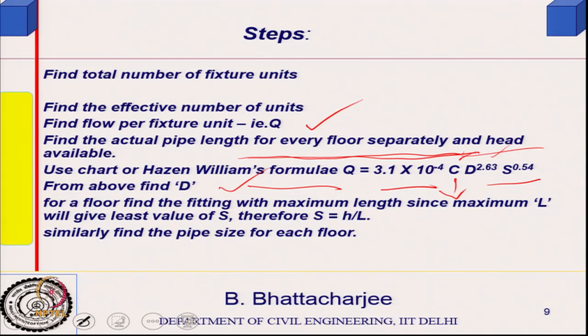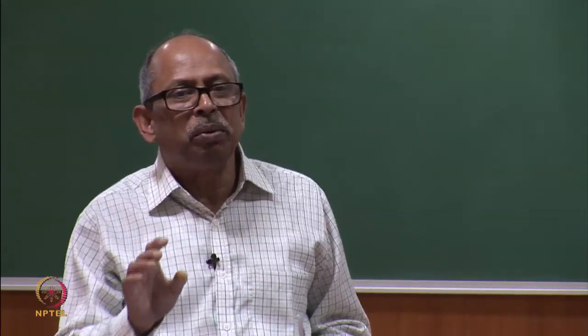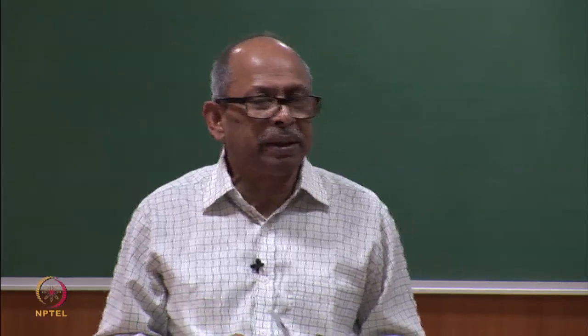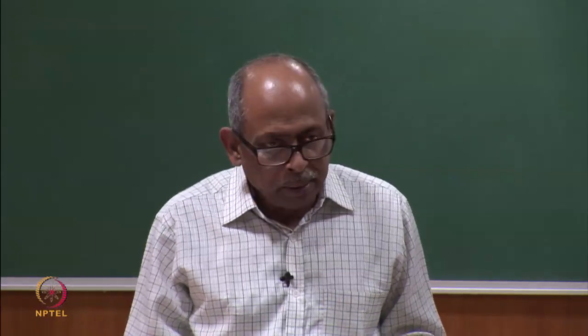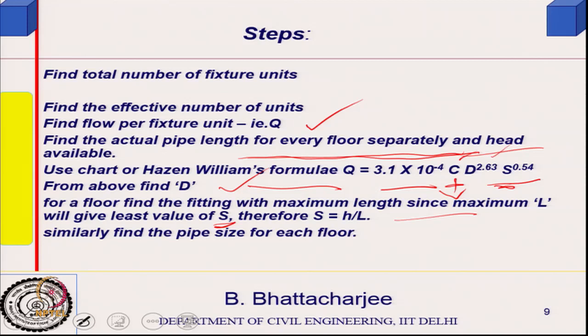The roughness coefficient C is known for the pipe type — for cast iron it is 100, and these values are tabulated. Since length and available head are known, D is the only unknown and can be found. For each floor, find the fitting with maximum length, which gives the least value of slope S. Use uniform pipe sizes as much as possible — taking the least S corresponds to the maximum D. Similarly, find pipe sizes for each floor.